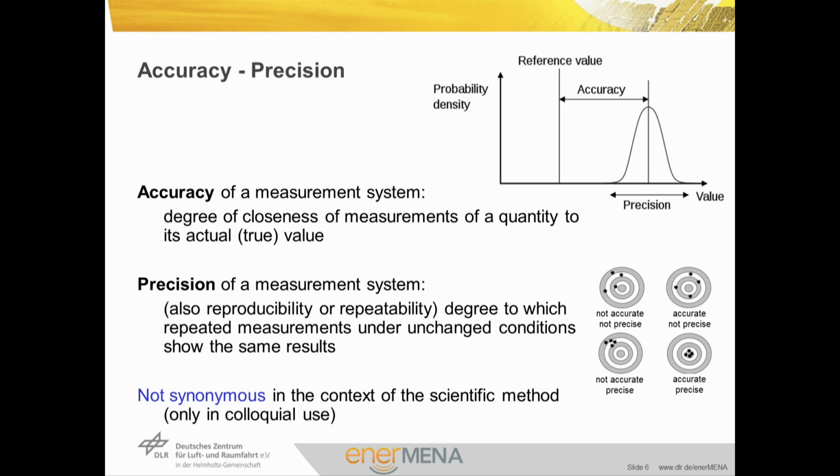At the same time as clarifying the meaning of accuracy and precision, this example indicates that they are not equally easy to detect from measurement data. While precision can be deduced from the data and its reproducibility itself, an assessment of accuracy requires the knowledge of the actual target value, which is hardly available. In practice, the accuracy of measurements can only be assessed by comparison to reference instruments of higher accuracy.